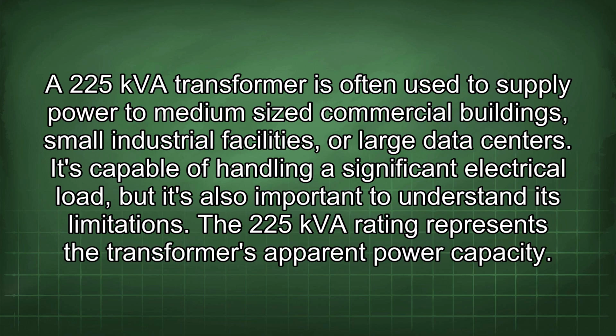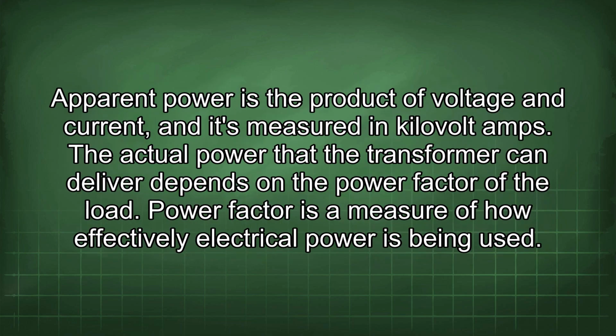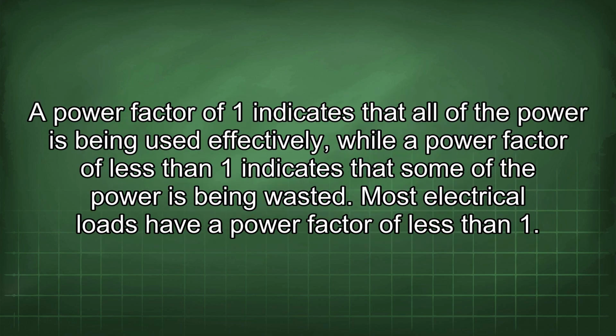The 225 kVA rating represents the transformer's apparent power capacity. Apparent power is the product of voltage and current, and it's measured in kilovolt amps. The actual power that the transformer can deliver depends on the power factor of the load. Power factor is a measure of how effectively electrical power is being used. A power factor of 1 indicates that all of the power is being used effectively, while a power factor of less than 1 indicates that some of the power is being wasted.